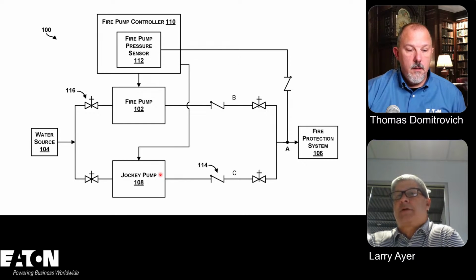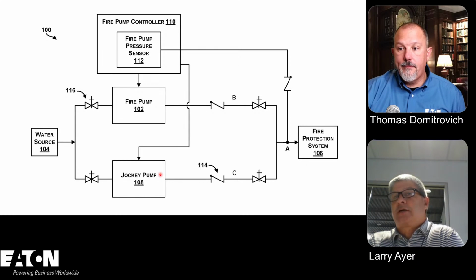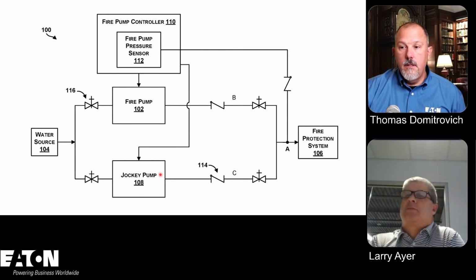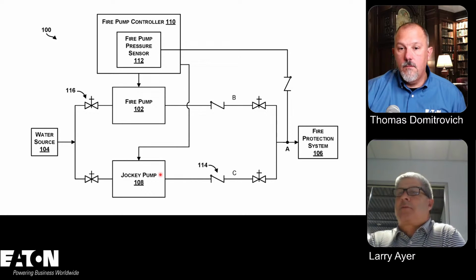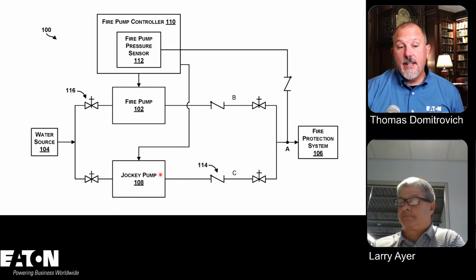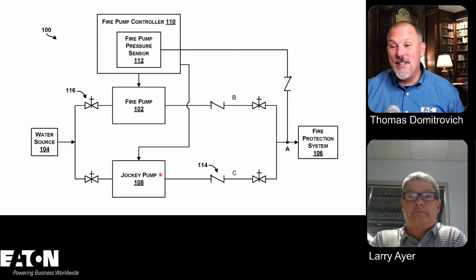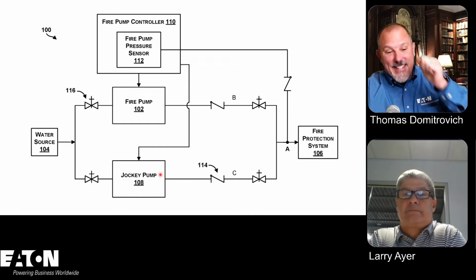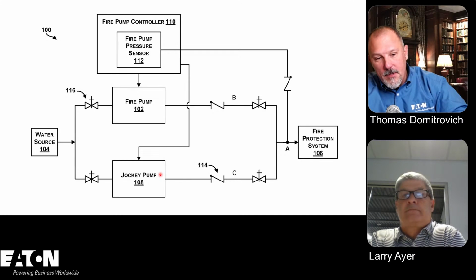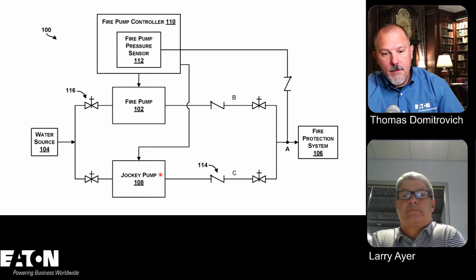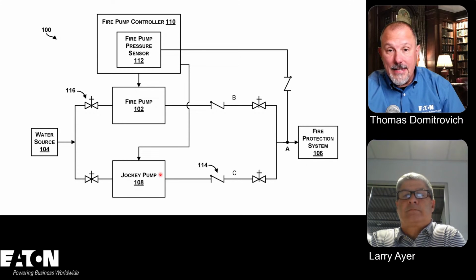And so you also have the controllers, whether it's a fire pump and a jockey pump controller. Those things sense pressure and tell those two pumps how to operate and how to work together, and how to send alarms back to the fire alarm system. All right, so Felix has a good question. He says, is it required that the jockey pump be in the same feeder as the fire pump? And do we think that's a good idea?